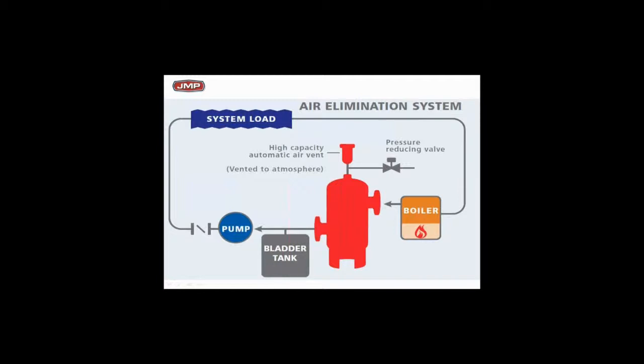We pressurize the bladder tank, therefore it runs quite well. This is a great system — probably 90 to 95% of new projects are going in this way. A fine note: try to avoid putting the bladder tank directly under the pipe or directly over the pipe. We don't want trash plugging anything up and we don't want an air pocket trapped there.